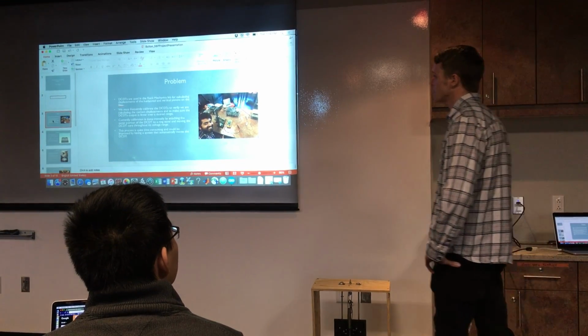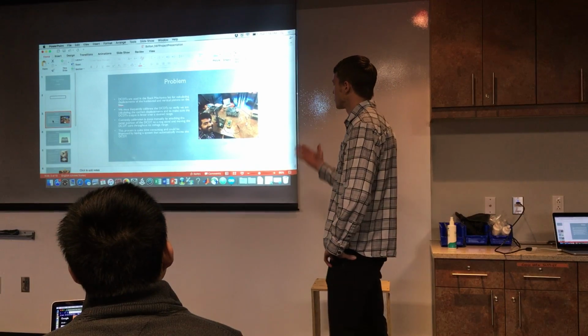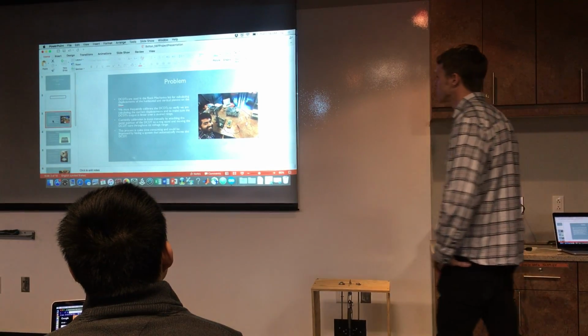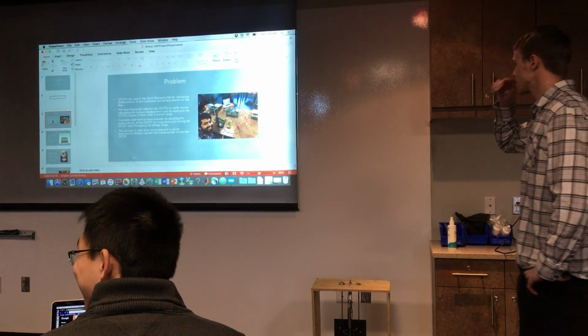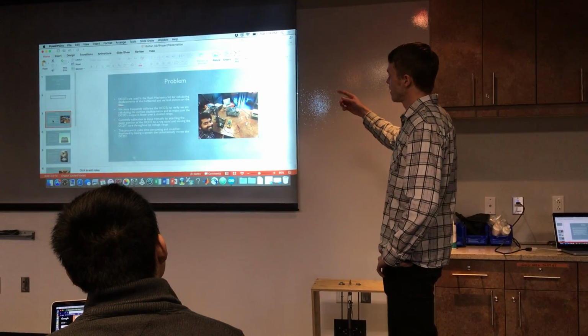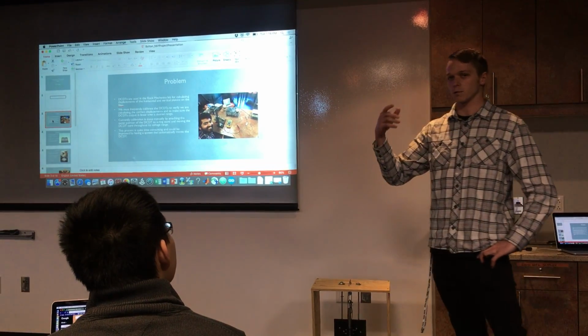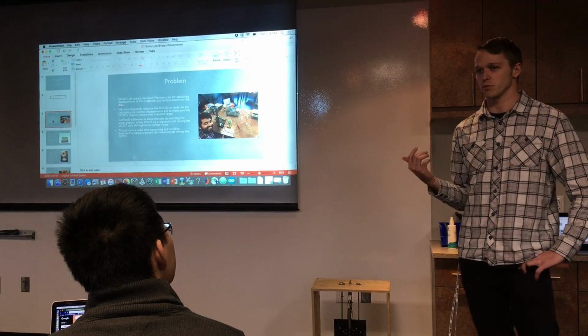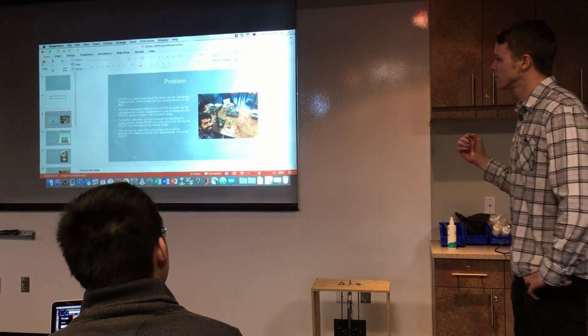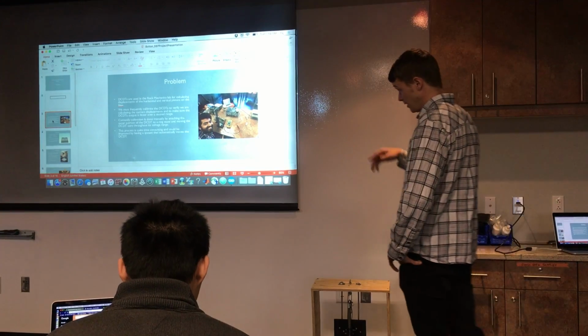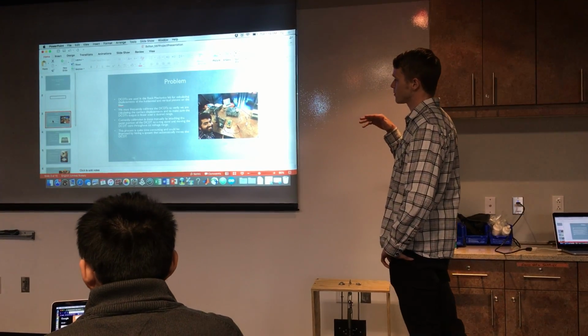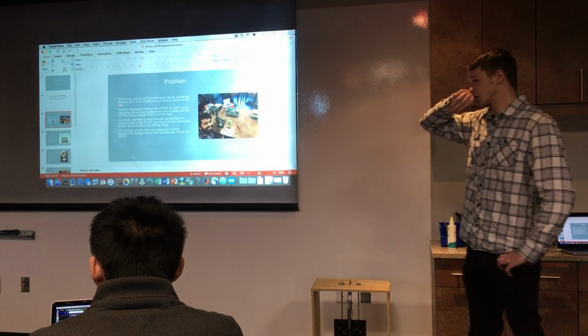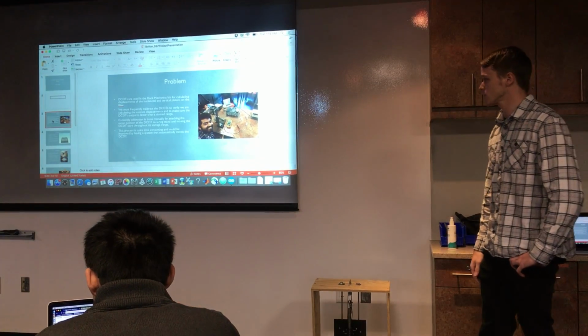Currently, the way we do calibrations, you can see someone here really enjoying doing this. The basic idea is to have a ring stand which holds the outer part of your DCDT, and then you move the core throughout the voltage range in 1 millimeter increments, recording the voltage at each position.